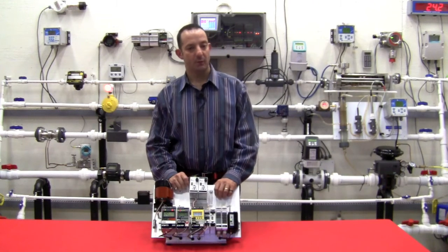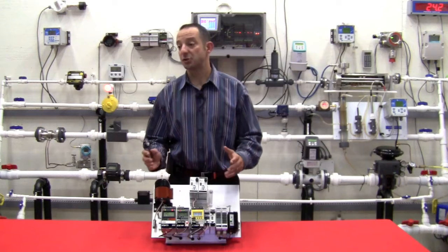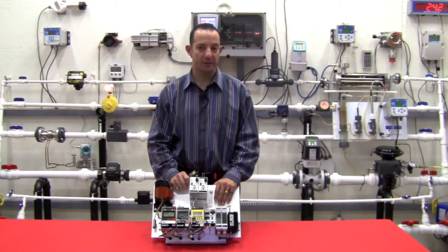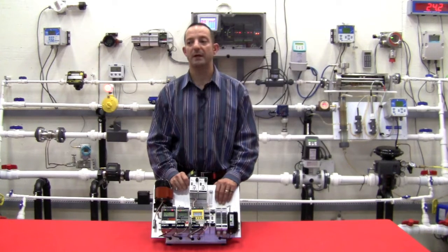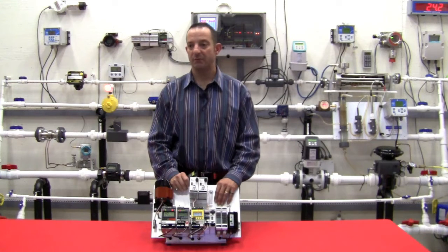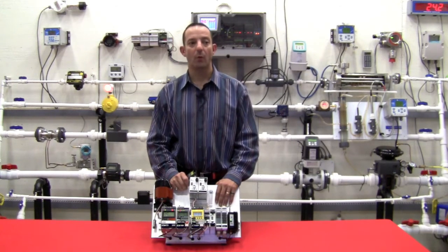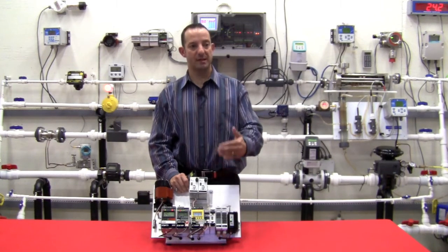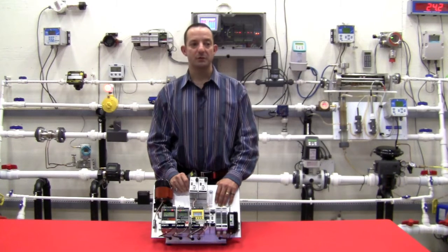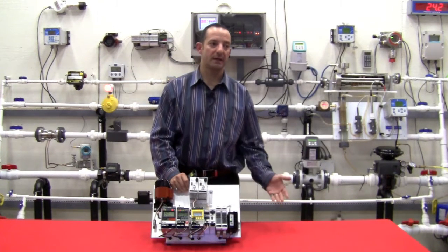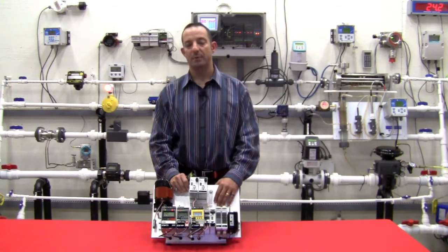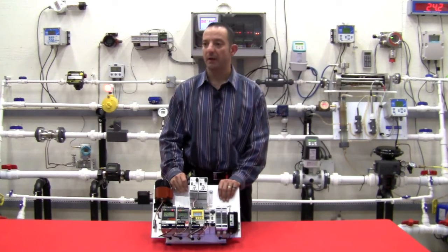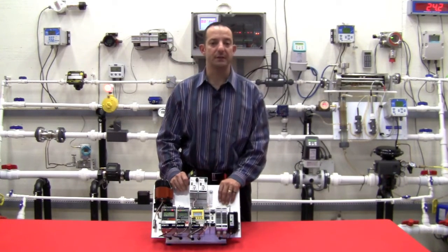The third application that we cover with our isolators and converters is just straight conversion. Often in power plants and other older industrial environments, there's legacy equipment that might give -10 to +10 volts DC outputs, or 1 to 5 volt DC outputs, and you want to convert that into 4 to 20 milliamp standard analog signals. Because this lowers the cost of getting that information into the control system, because if everything coming into the control system is 4 to 20 milliamps, the input cards are cheaper and usually, or maybe, higher density.